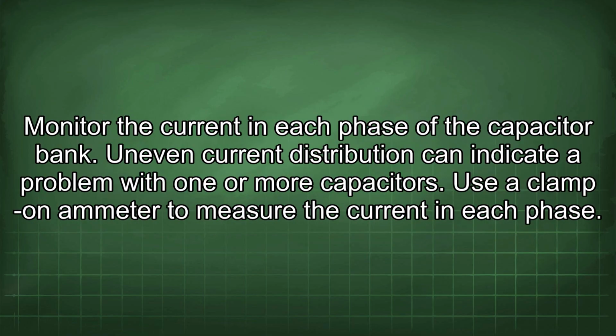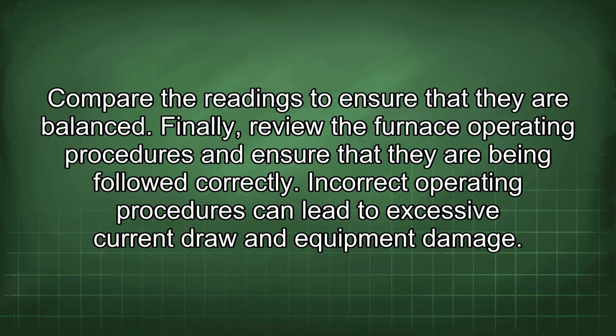Monitor the current in each phase of the capacitor bank. Uneven current distribution can indicate a problem with one or more capacitors. Use a clamp-on ammeter to measure the current in each phase. Compare the readings to ensure that they are balanced.